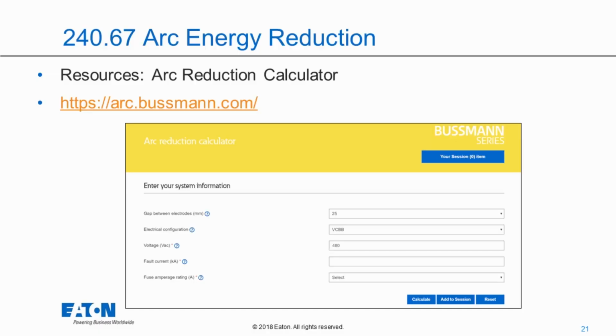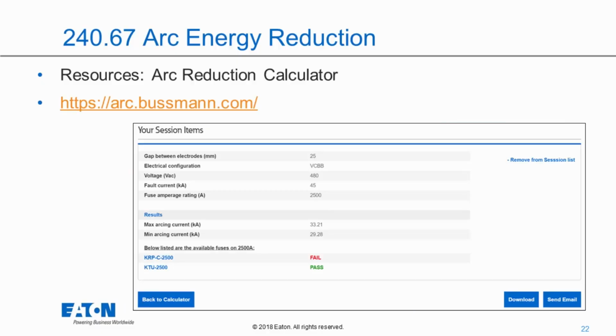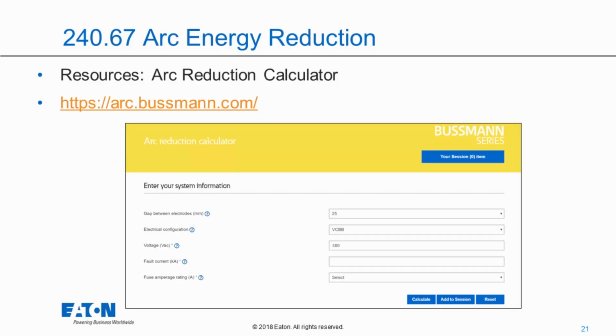So if you look at the different parameters here, I'm going to go right to the results because I think it's easier to see. You have the gap between the electrodes, and that depends upon the equipment types. For instance, if you had a molded panel board, the gap you would choose would be 25. That's what I've selected here. So panel boards and switchboards, the gap would be 25 millimeters. And if you look in the previous slide, I can go back to that real quickly, you'll see little informational notes, little question marks in a circle. If you hover over that, it'll give you guidance on what that gap means.